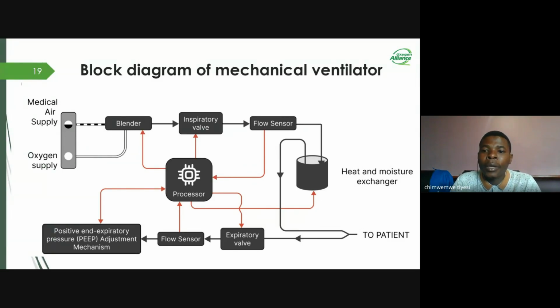Firstly, there is a medical air and oxygen source, which provides a steady supply of air and oxygen. Then there is a blender. The blender's purpose is to mix these two gases. After the blender, we have an inspiratory valve. When this valve opens, it lets a fresh gas mixture from the ventilator into the patient's lungs. Then we have a flow sensor. The flow sensor's purpose is to measure the amount of gas being delivered to the patient.